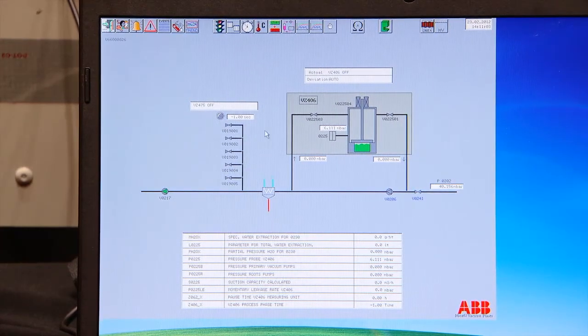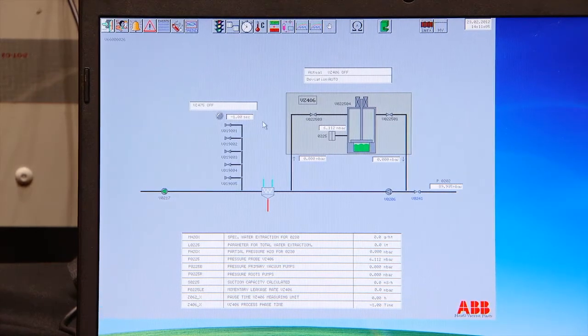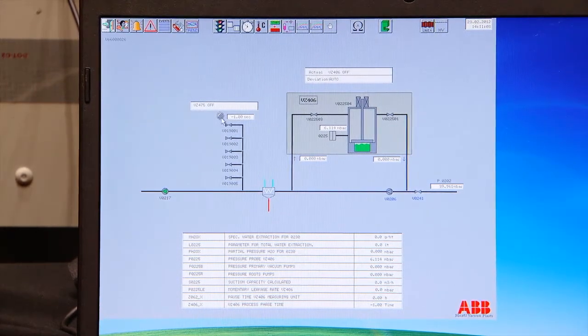To make this measuring is quite simple. You click on this gray button once, it starts, and it will start taking the measurement. We are using the pressure sensor inside the VZ406 for this case. That's why it's important that the high pressure side of the VZ is connected to the line, as well as the VZ475 is connected to this line.